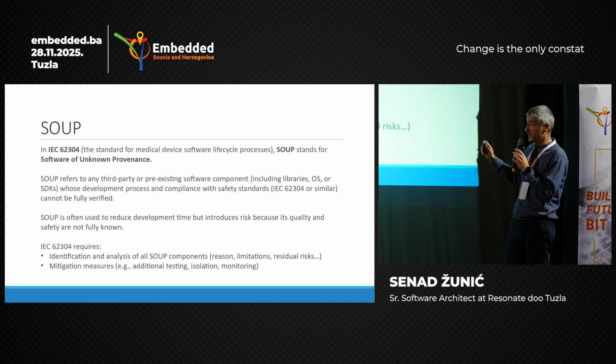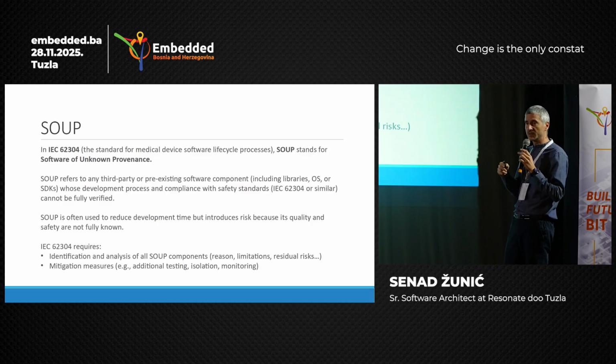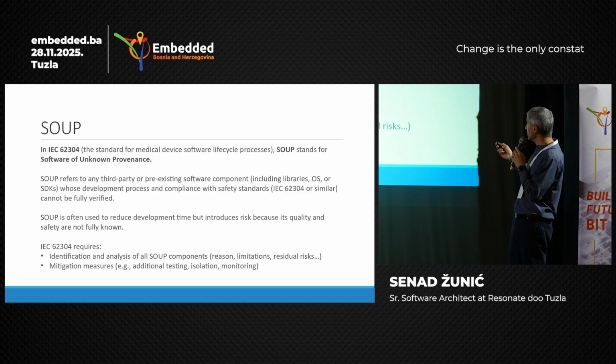So there's no way you can guarantee a third-party component unless it's certified. You need to watch for that. Is it built with the compliance and safety standards of, say, 62304? I'm saying this especially because of Arduino things, which are perfect for prototyping, but they are completely untested libraries that you take. We use them, it reduces development time, but it introduces risk because the safety and security are unknown. Be careful there. So while building medical software, for every sub-component that you use, you need to identify and analyze every single one of them.